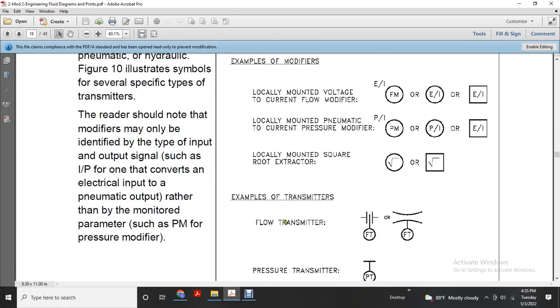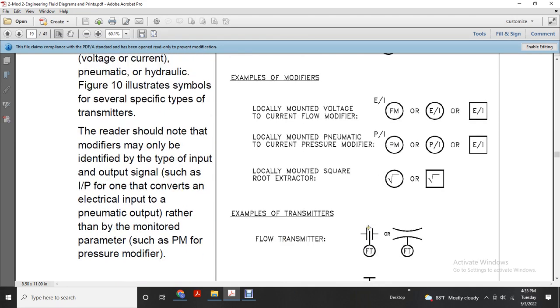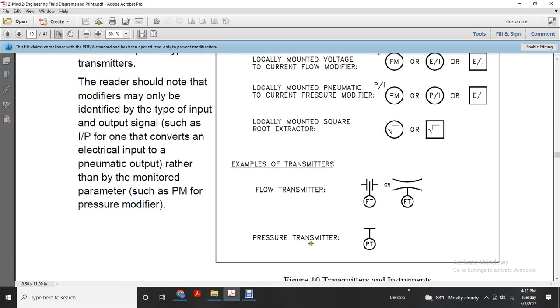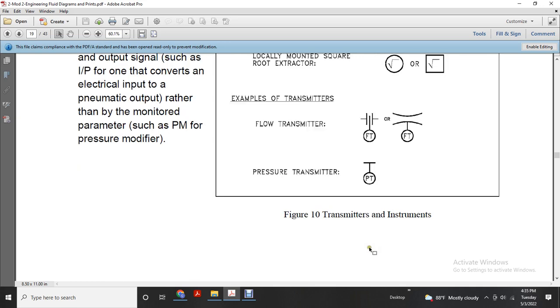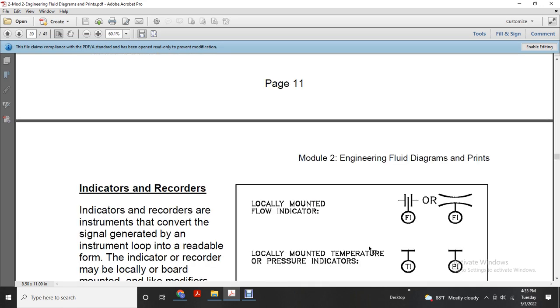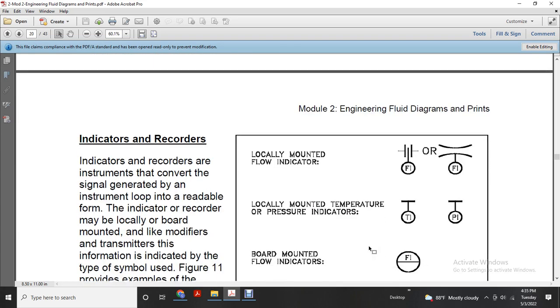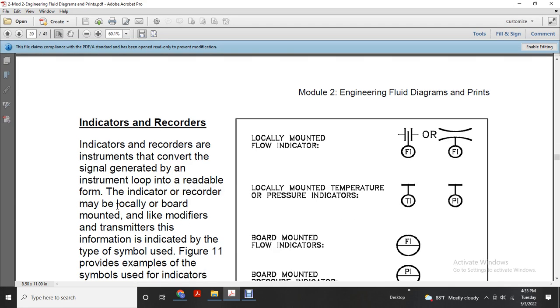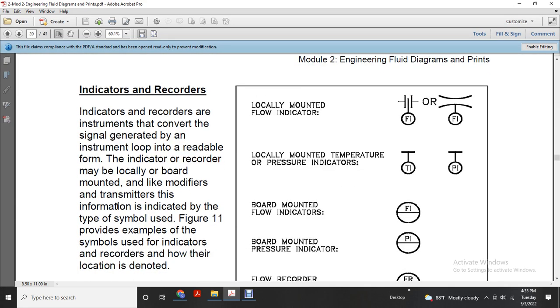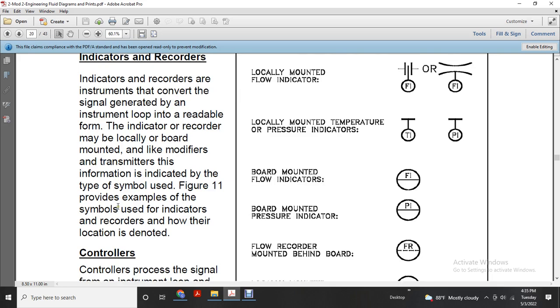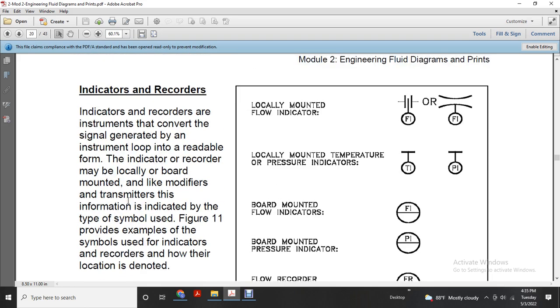Examples of the transmitter: flow, showing the restriction or venturi, and FT, flow transmitter; and the pressure transmitter, also with a bulb to the T junction. Indicator recorder: the indicator recorder is the instrument that presents the signal generated in the instrument loop in a readable form. The indicator recorder may be locally or board mounted, with the modified transmitter information indicated within the type of the symbol. Figure 11 provides examples of the symbols used for an indicator or recorder and how the location is denoted.